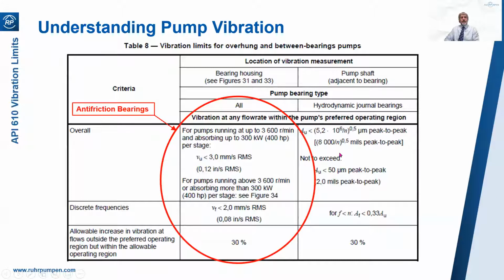Here is table 8 from API 610, and it shows the vibration limits for anti-friction ball bearings. So for flow rates within the pump's preferred operating region, remember the preferred operating region is from 70% to 120% of the best efficiency point flow, 70 to 120%. So within that range, the vibration velocity must be less than 3 millimeters per second or 0.12 inches per second, root mean square.